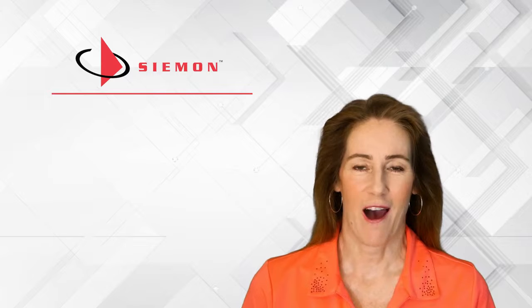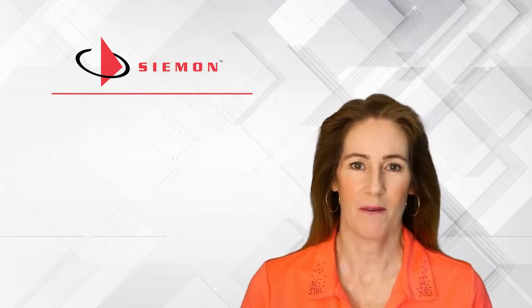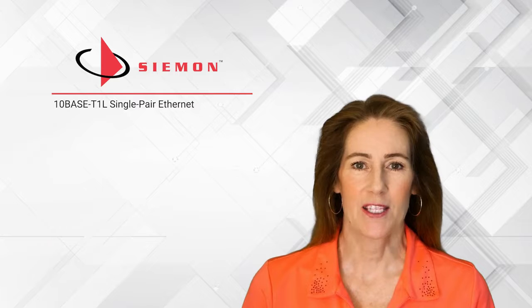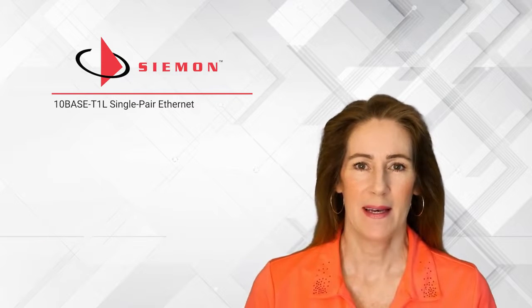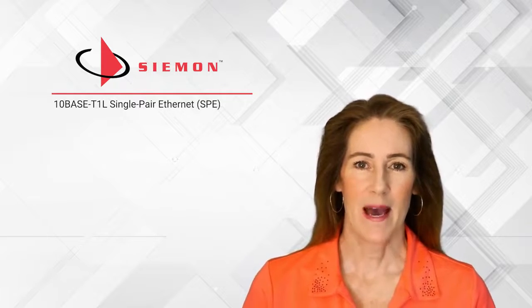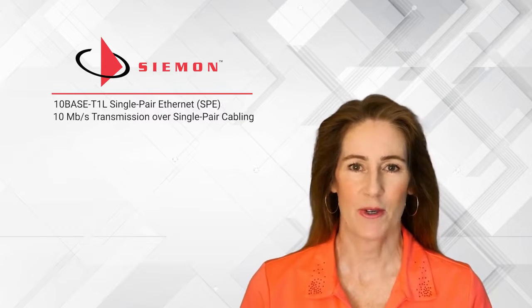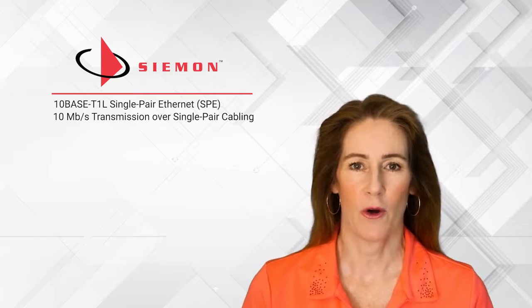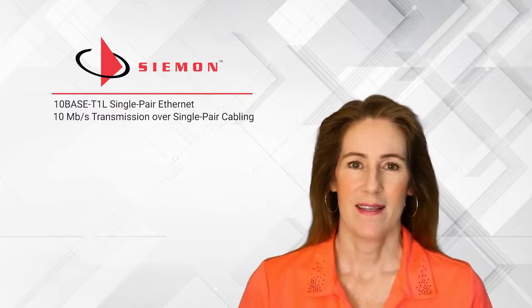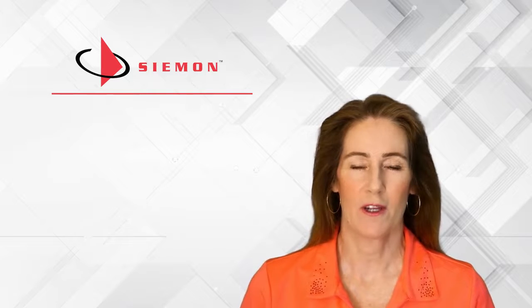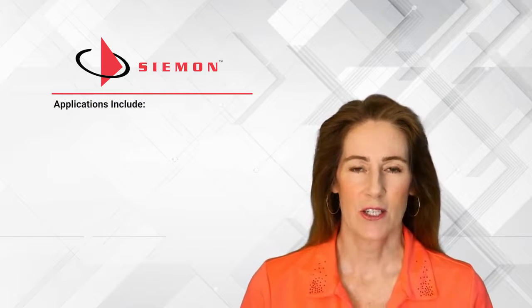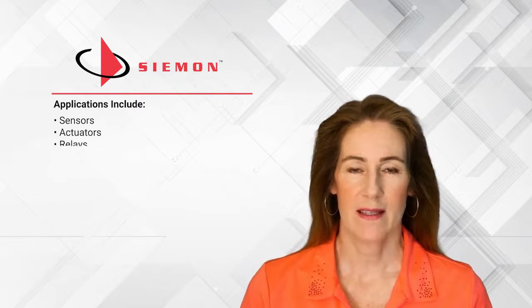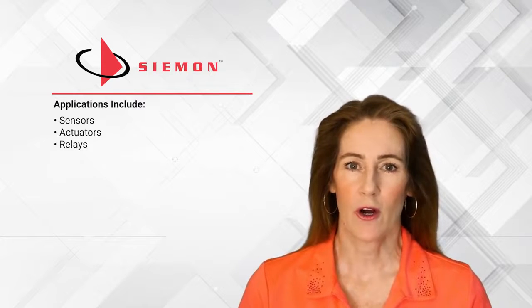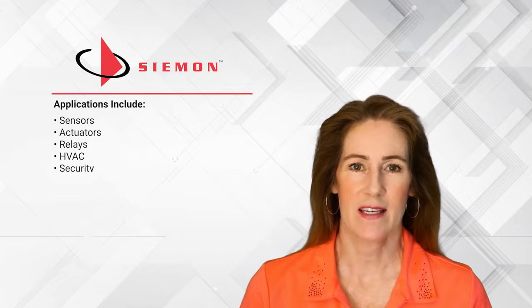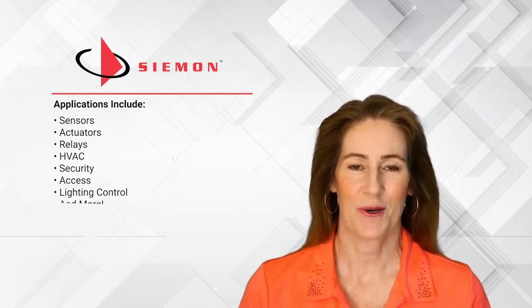This project defines the operating parameters for 10BASE-T1L single pair Ethernet, an application which is commonly referred to by its acronym SPE. The SPE application supports 10 megabit per second transmission over balanced single pair cabling for operational technology, or OT, applications. These applications encompass a wide range of low speed and field bus devices such as sensors, actuators, and relays, devices commonly used for building automation applications such as HVAC, security, access, and lighting control.